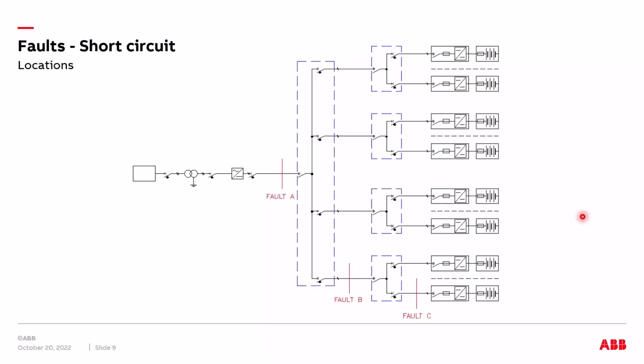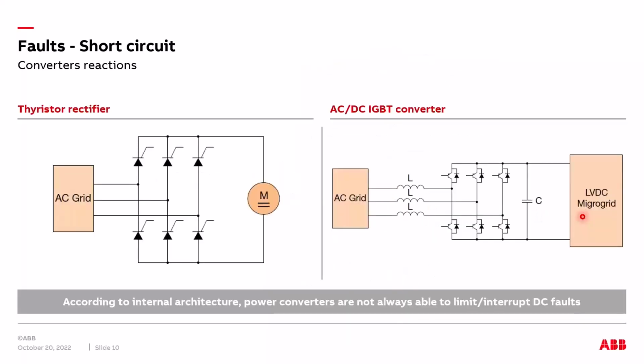So let's talk about, first of all, fault A. If we would like to talk about fault A, we have to consider, as I was saying, first of all, the internal architecture of the AC-DC converter. There is a conventional wisdom for which if there is an AC-DC converter, the fault is no more an issue. This statement is true in some cases, in particular if the fault occurs on the AC side of the converter. But if the fault occurs on the DC side of the converters, this statement is not always true, and it depends on the internal architecture of the converter.